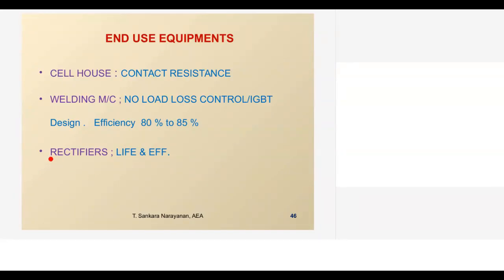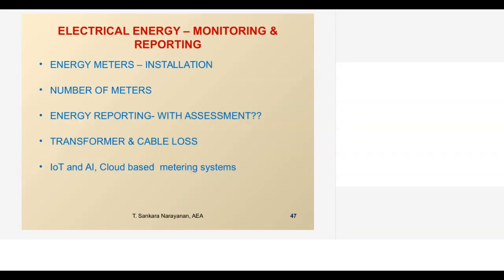For certain plate type rectifiers, we have to refer to the supplier manual to see how the efficiency drops over the years of operation. Some of the rectifier companies give around a 5 to 6 percent drop in design efficiency based on the life of operation. Then energy meter installation.